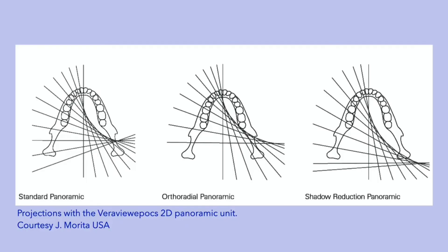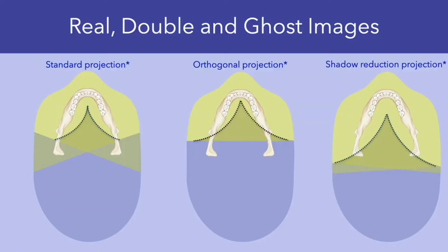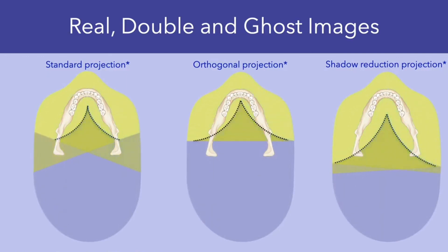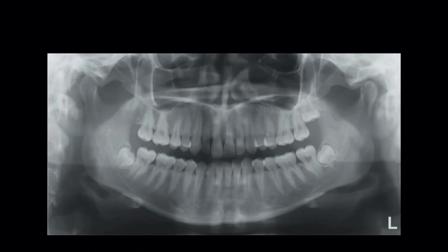Modern panoramic machines provide options for different panoramic projections. Modifications to the standard projections are created by changing the path of the rotation center. As a consequence, the zones where real, double, and ghost images are produced will also vary. Be aware of this when interpreting panoramic radiographs made with non-standard projections. These non-standard projections are of value in specific situations. The orthogonal projection, for example, allows us to visualize the teeth with less horizontal overlap. And with the changing zones in the shadow reduction projection, there is less superimposition of structures over the jaw. When interpreting a panoramic radiograph, it is important that you be familiar with the principles of image layer formation and the formation of real, double, and ghost images.